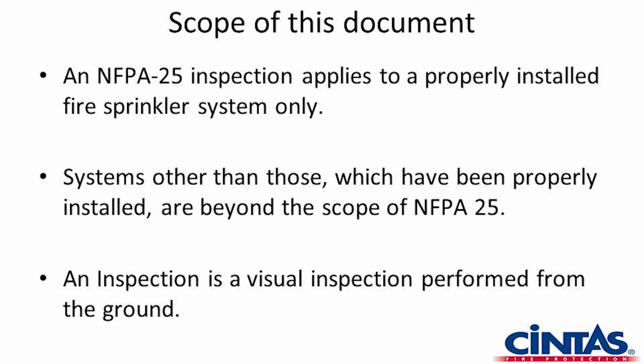The inspector generally will be licensed, but they won't be certified in design and inspection normally. Systems other than those which have been properly installed are beyond the scope of NFPA 25, meaning 25 is the standard for inspecting, not for installing.